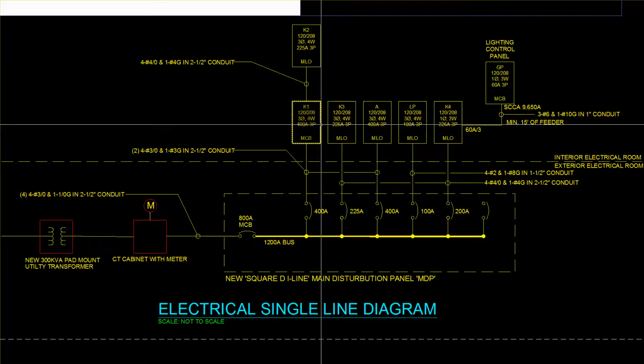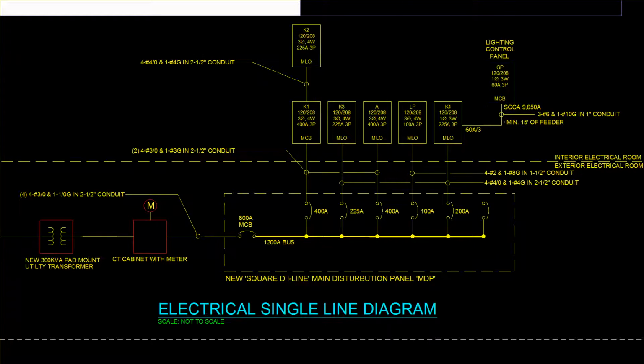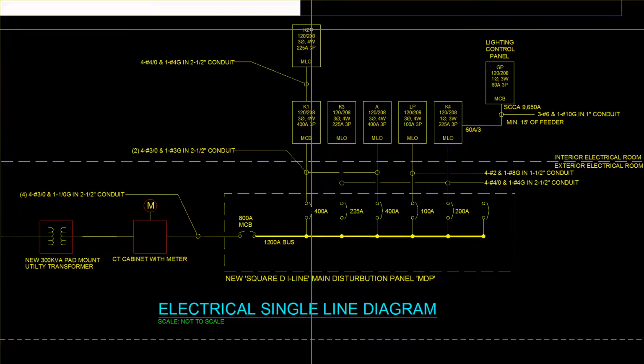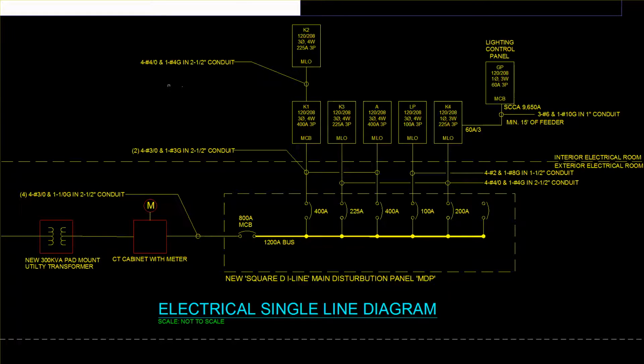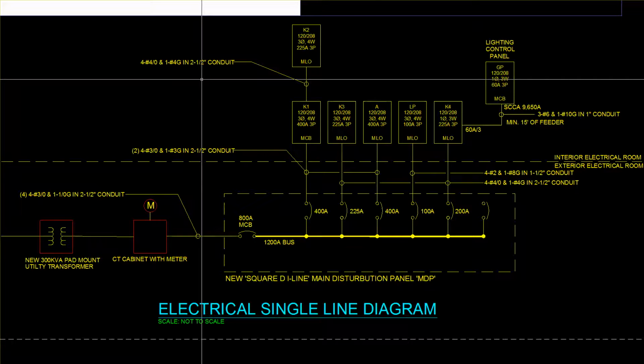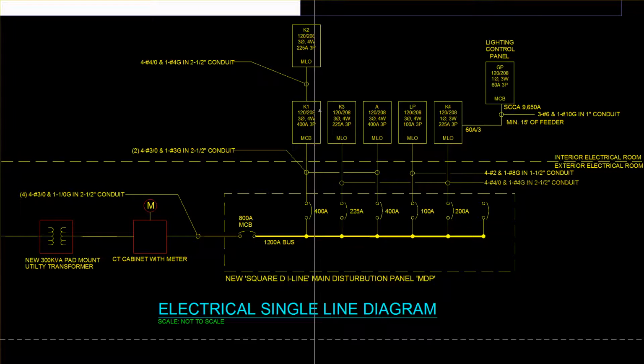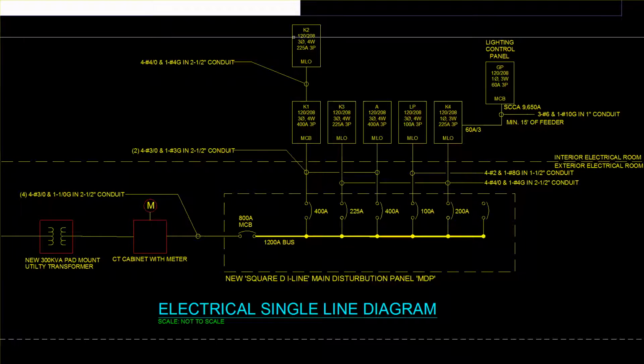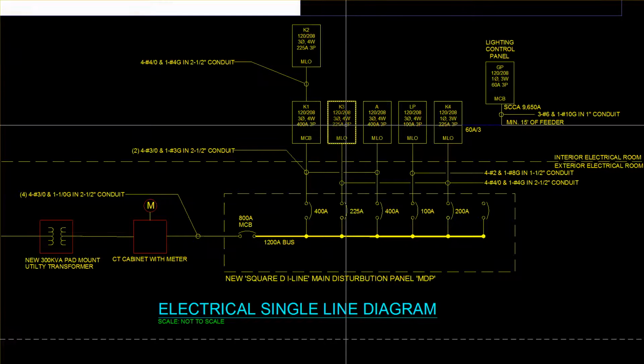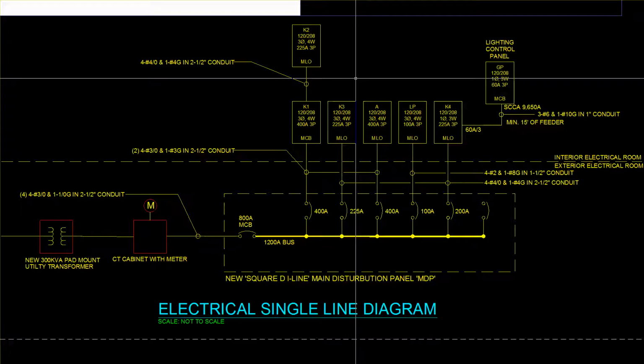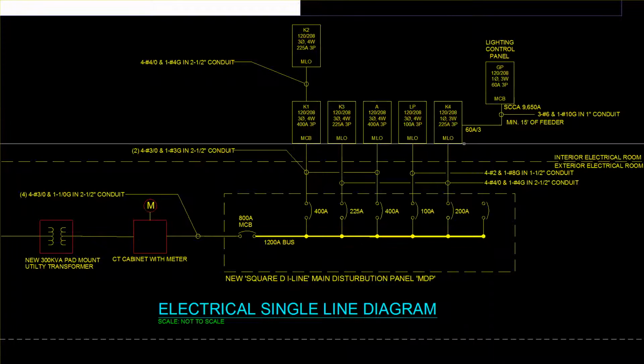And then you'll see panels that have subpanels. You see there are 2 subpanels being fed by other panels here. So here's a subpanel, K2, which is a 225, and it's being fed with 4 4/0. And so it's a similar configuration to what you see down here. So that's panel K1, K2. Those are kitchen panels. And there's K3, which is a 225 fed directly from the MDP.